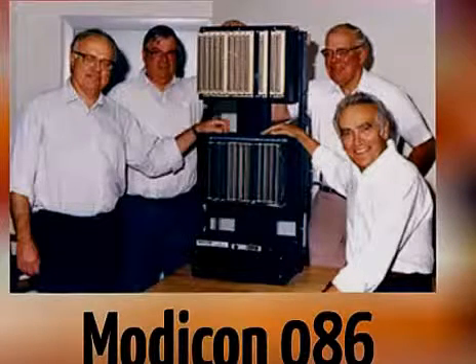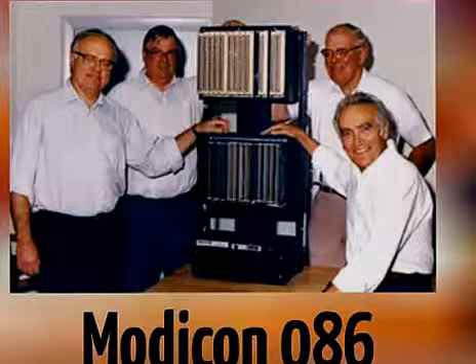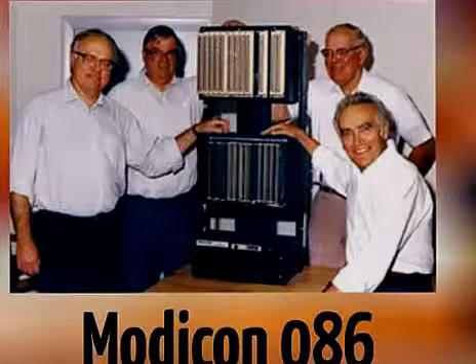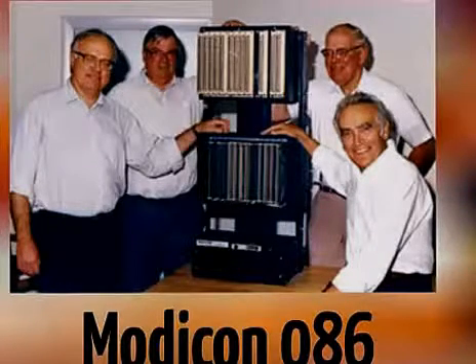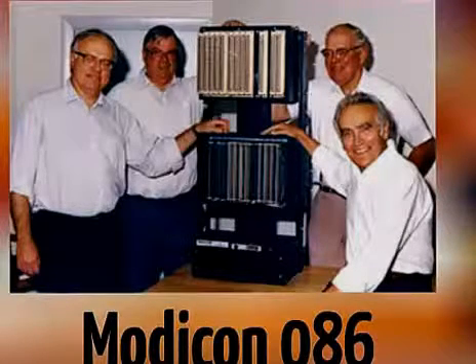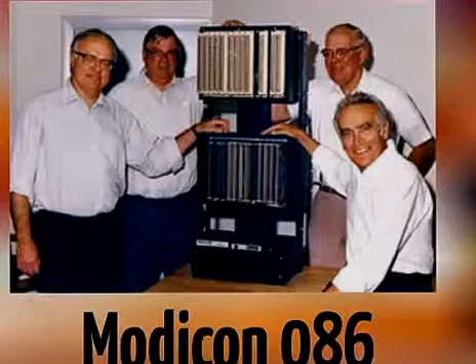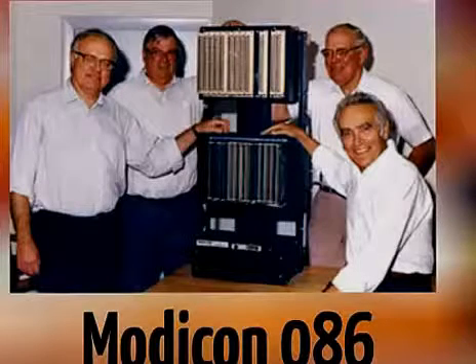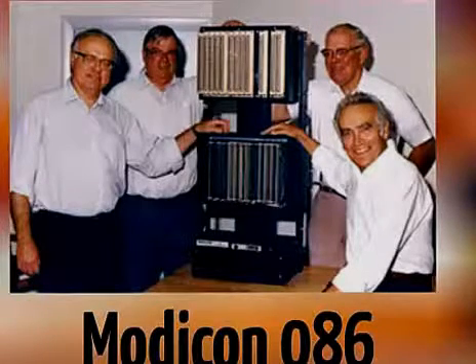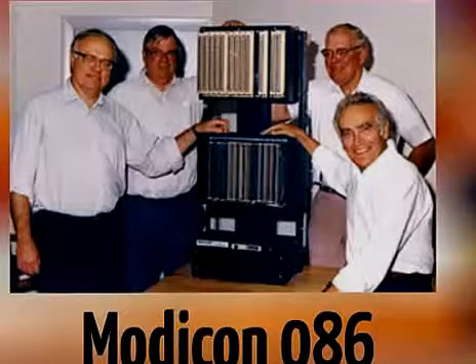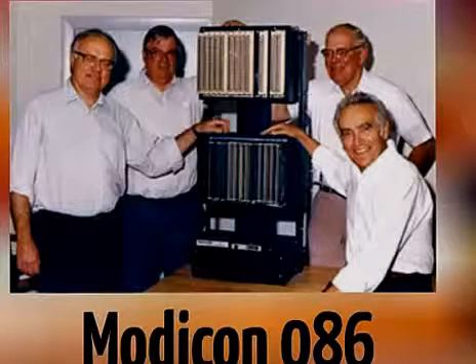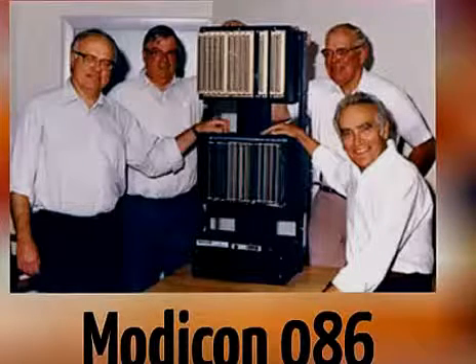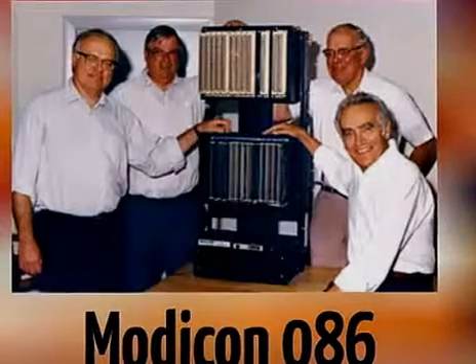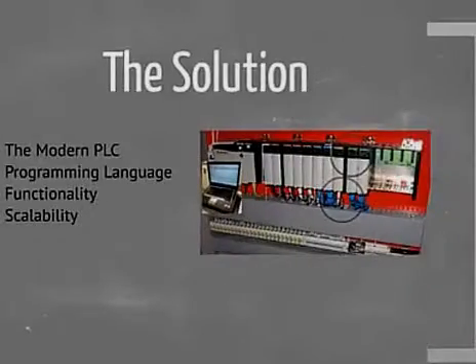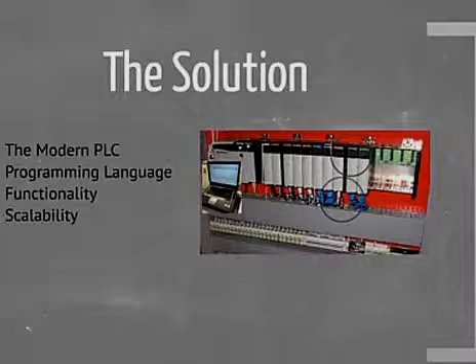We can actually consider a PLC to be a box full of hundreds or thousands of separate relays, counters, timers, and data storage locations. They don't physically exist, but rather they are simulated and can be considered software counters, timers, and so on. A PLC has many input terminals through which it interprets high and low logical states from sensors and switches. It also has many output terminals through which it outputs high and low signals to power lights, solenoids, contactors, small motors, and other devices lending themselves to on-off control. Fit into a control cabinet, a PLC takes up little room, especially considering the equivalent space that would be needed by electromechanical relays to perform the same functions.